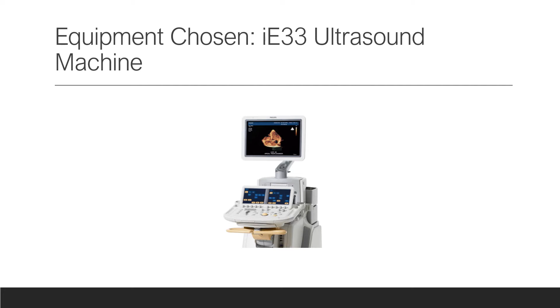Troubleshooting was done where it was observed that the data was not being sent, thus resulting in the data not being deleted. The machine only contains a maximum storage of 500 gigs. Therefore, in order for data to be deleted, it must be backed up and stored at all times. From this, an understanding was gained on the DICOM standard, which is the international standard to transmit, store, and process display medical imaging.